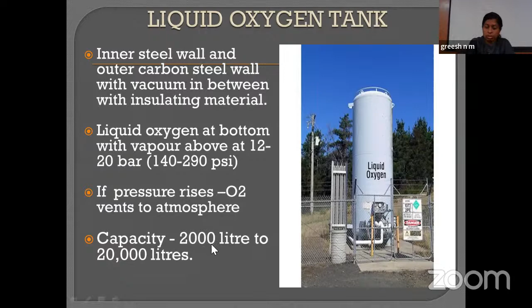The oxygen tank has around two valves. These are two filling valves to fill the lower portion as well as the upper portion. One is connected to the lower portion of the tank, the other to the upper portion. There is a pressure gauge indicating the pressure in the tank, and there is also a pressure relief system. Whenever there is a mild buildup of pressure in the cylinders, we can open the valve manually to decrease the pressure. But there are also pressure valves which open spontaneously, in the condition where there is an extensive buildup of pressure in the cylinders.